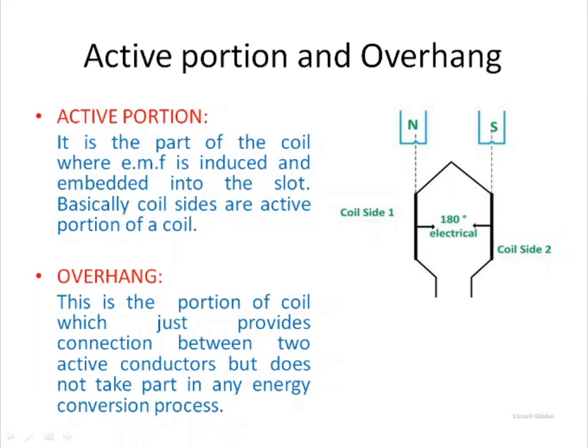Active portion and overhang of a coil. The active portion is a part of the coil where EMF is induced and it is embedded into the slot. Basically, the coil sides are the active portion of a coil. The overhang is the portion of the coil which just provides a connection between two active conductors but does not take part in any energy conversion process.